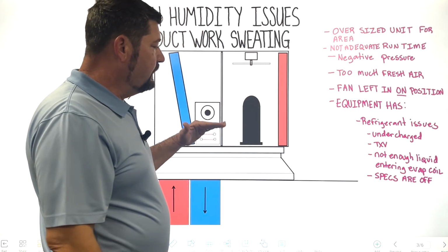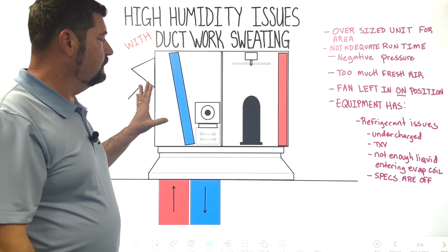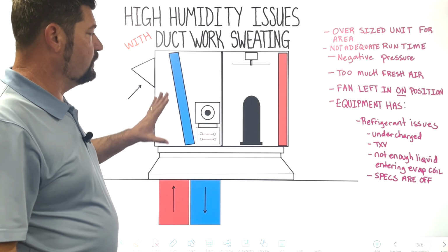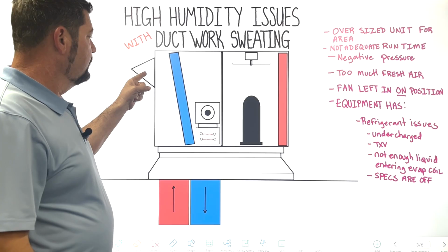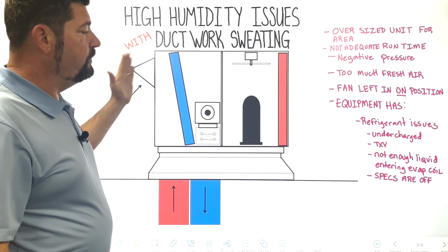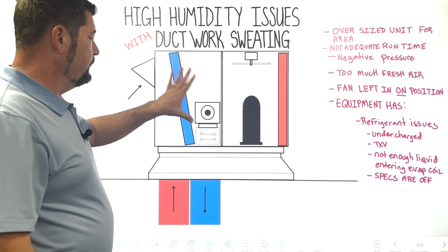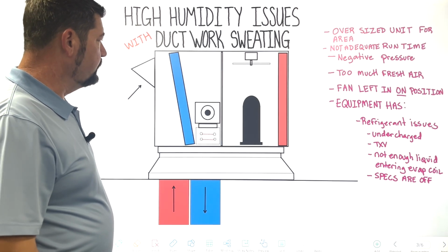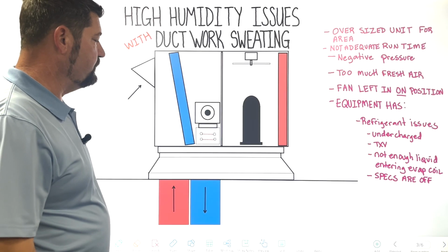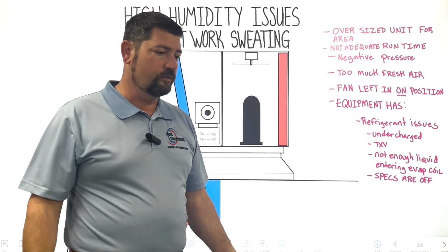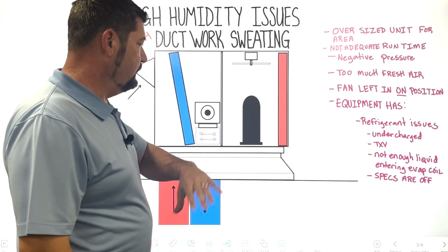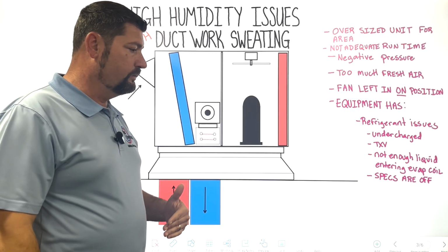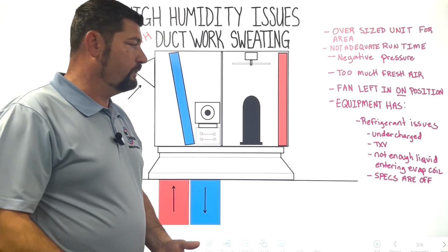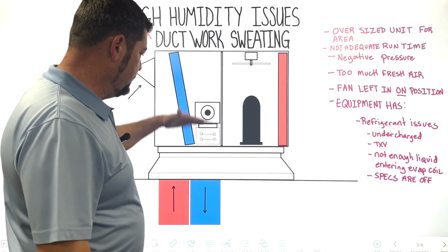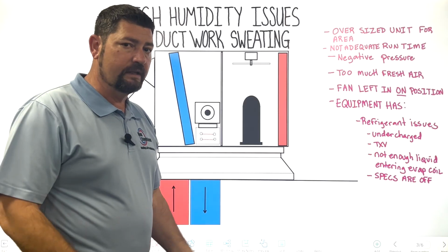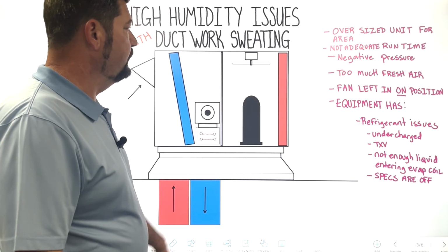And so we start hitting those dew points, and a lot of the times, we've seen this in many structures where RTUs wind up getting replaced, and the outside fresh airs are not added back to it, or they're not ordered when the equipment's ordered and they're not put on. So that's actually a very big deal, and it's supposed to be caught on a building inspection when you pull your mechanical permit. The inspectors in that county that are there to sign off that things were done to the mechanical codes, that's one of the things. Just like you can't just sit these on the curbs, you have to anchor them down because there's wind and you want to mitigate against any strong gusts of wind.